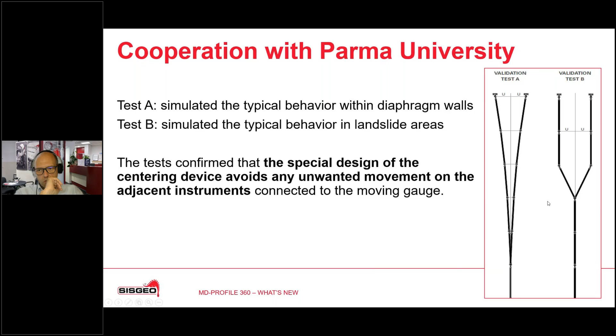Let's take a look at the sketch on the right side of this slide. In validation test A, Parma University moved the string of MD Profile like it moves, for example, in a retaining wall or in a diaphragm wall, okay? And in validation test B, Parma University moves the string like in a landslide. So the bottom part is vertical, no movement, the upper part moves rigidly, and here we have the shear movement of the landslide. So Parma University proved that the movement of this gauge alone doesn't have any effect on the adjacent instrument. So this sensor and this sensor don't feel the movement of these gauges. Very, very, very important.